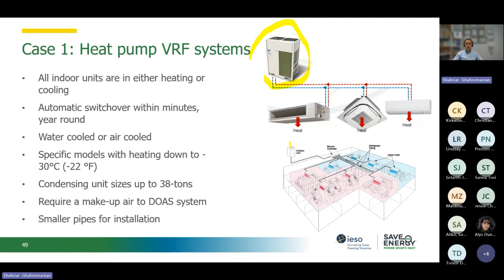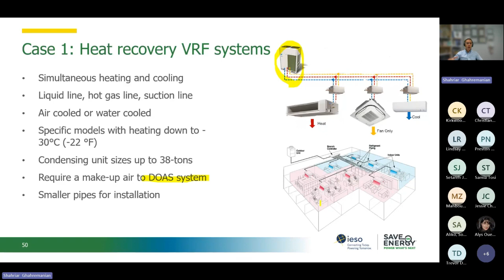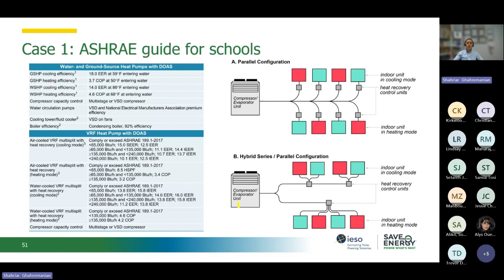If we need a larger system, then maybe air cooled or water cooled heat pumps on the roof would be the unit that we need for our facility. But if we go with a VRF system, then the outdoor air system, which is required for the ventilation of the building, is needed because we are just running the refrigerant for heating and cooling purposes. So now we need to bring outdoor air for the ventilation. Again, ASHRAE has numbers for the schools, so that's a good one, and different configurations like a parallel configuration or hybrid parallel configurations. Again, this is about how to combine the units that we have with the outdoor unit.